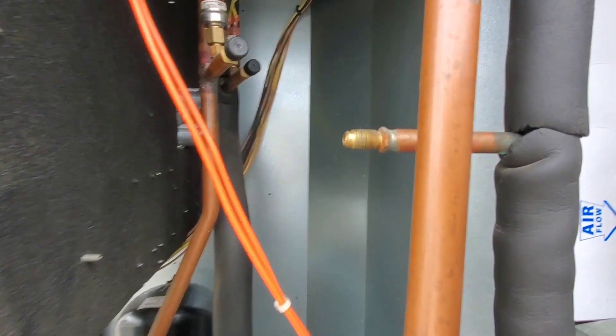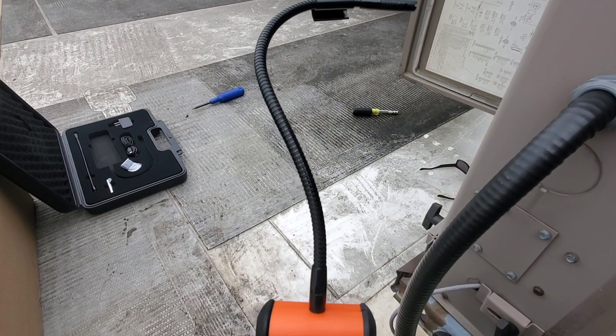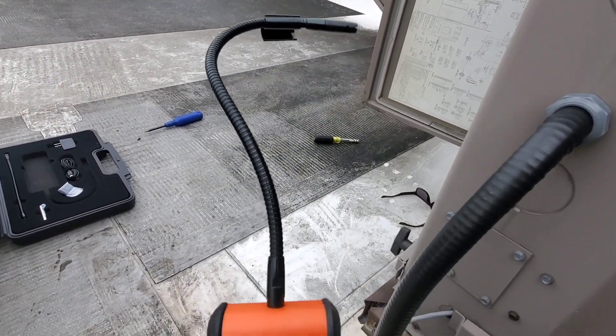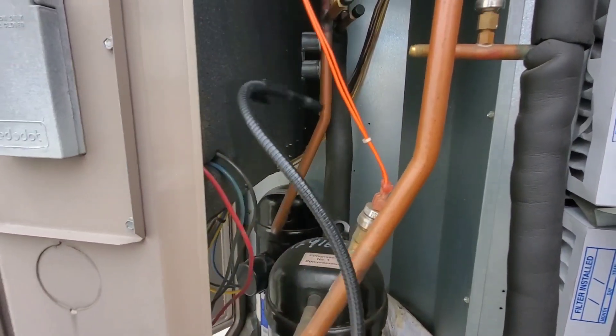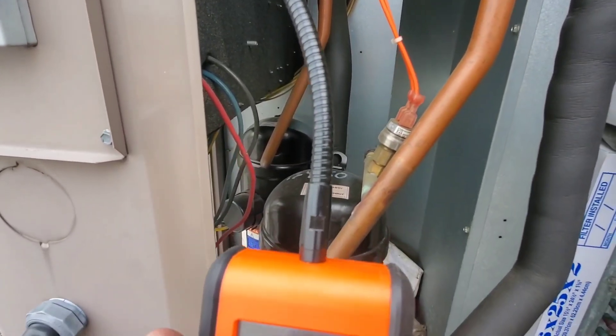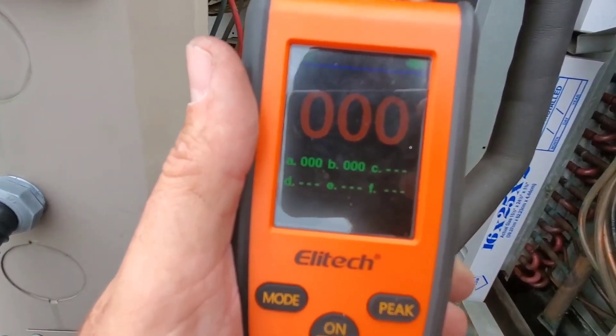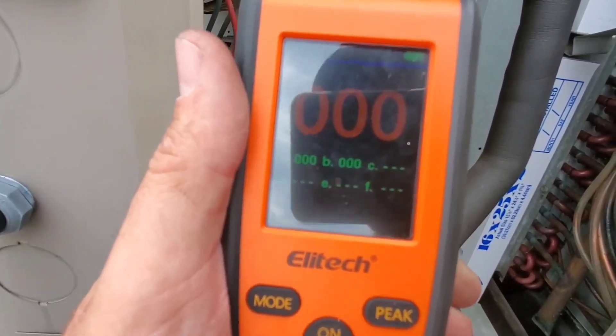I've pulled the cap off of this valve core. The gooseneck is very flexible, so we can get it into unusual places — getting in there is not a problem. Let's see if we register anything here... we are not at the moment. So that valve is actually not leaking.